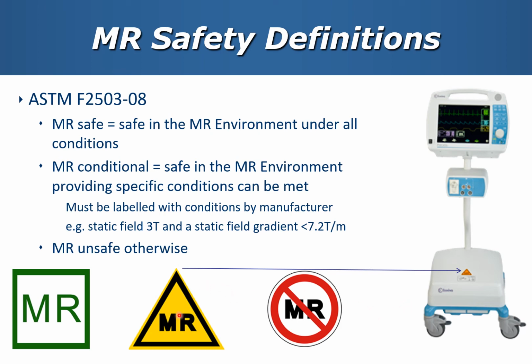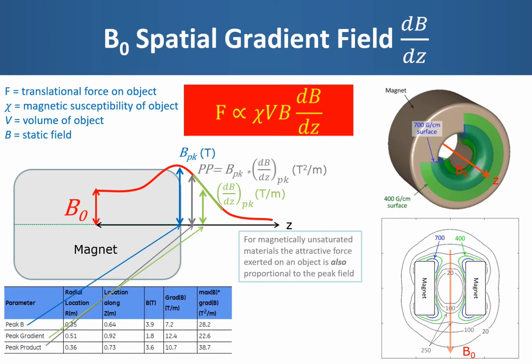Such labelling also extends to devices that are implanted in the patient, whether they are passive, such as a hip replacement, or active, such as a neurostimulator. The main risk for ferromagnetic projectile incidents is the spatial gradient field, or how the magnetic field falls off with distance from the magnet. The use of actively shielded magnets means that this field can reduce quite rapidly with distance.